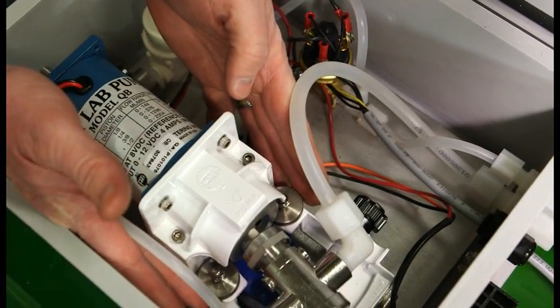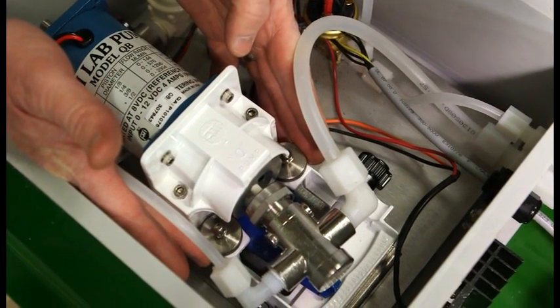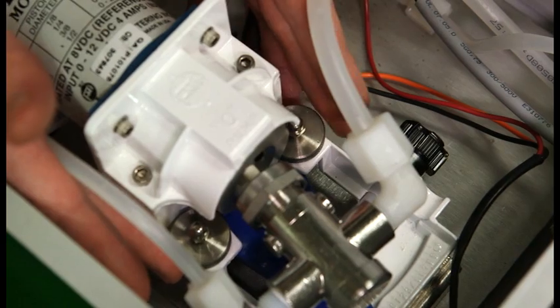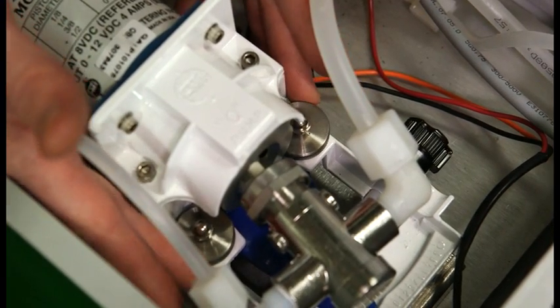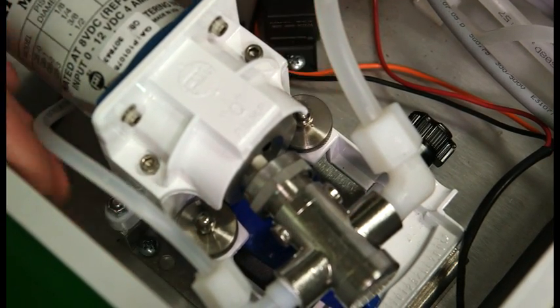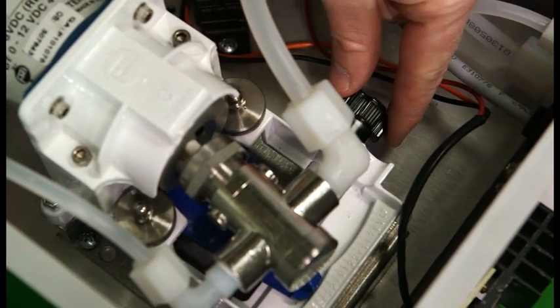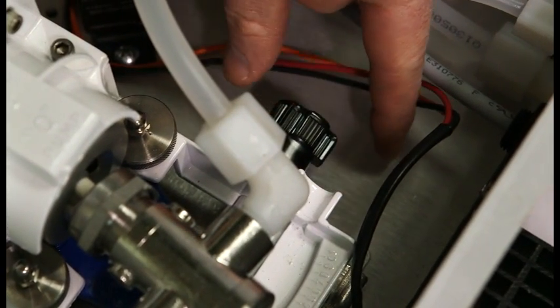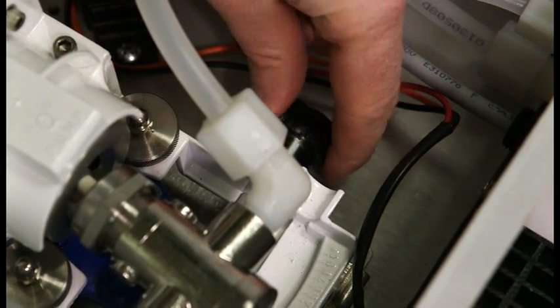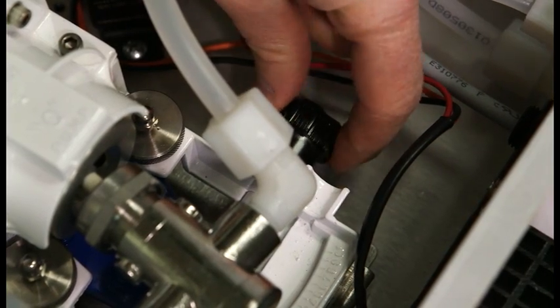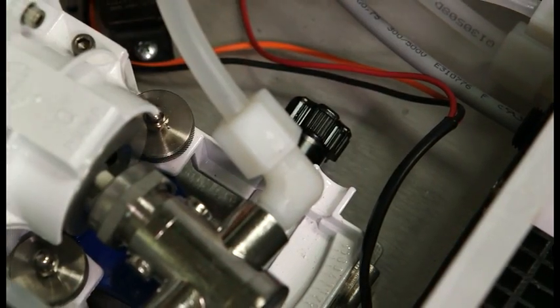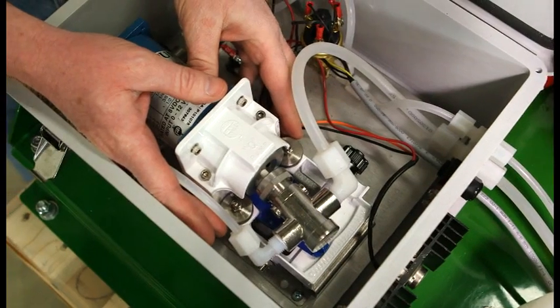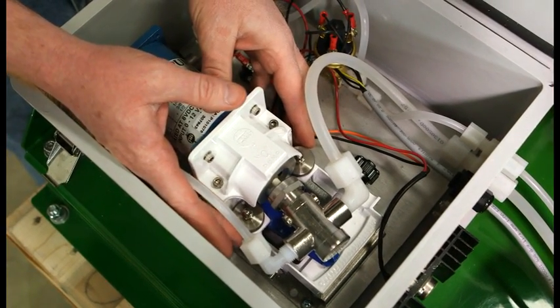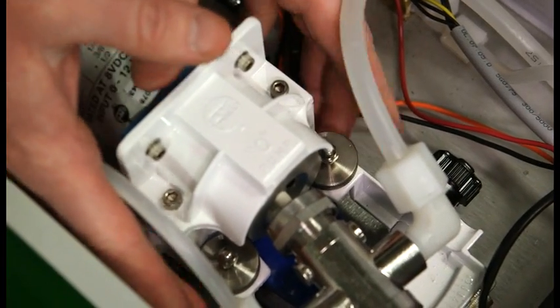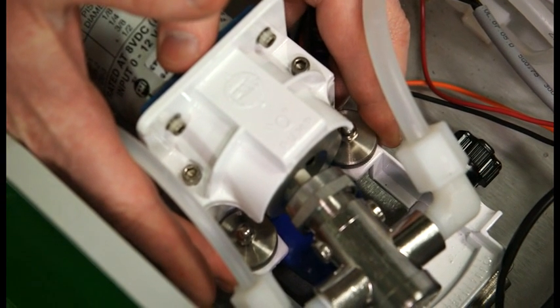Lastly, in our pump here, when we want to increase or decrease the amount of chemical, the first thing we want to do is loosen our set screws. Then we come here to our black knob, and as we increase or decrease the stroke of our pump, that will increase or decrease our flow rate. Once we've reached our desired setting, you want to make sure you turn your set screws and lock your pump back in place.